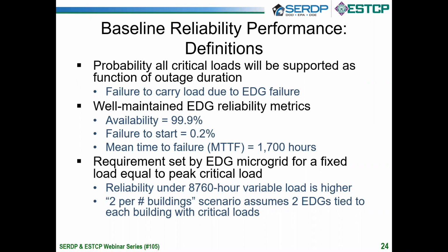Supported by ESTCP, NREL did a detailed analysis of existing empirical data that's been collected by both the Army and Navy to define what the performance of well-maintained generators are. And the numbers you've seen here are a result of that analysis. Availability of diesel generators is quite high. The reason they're quite high is that they're not called on that often, so the probability they'll be offline due to a failure is quite minimal. They're also quite available because traditional maintenance takes an hour at most, and therefore when you're considering outages that may run up to a week, they'll be put right back into service immediately.